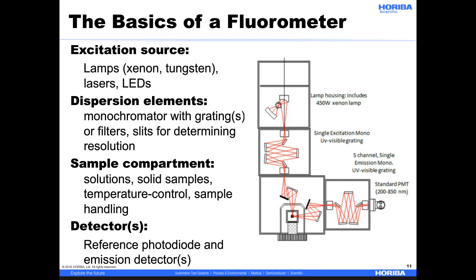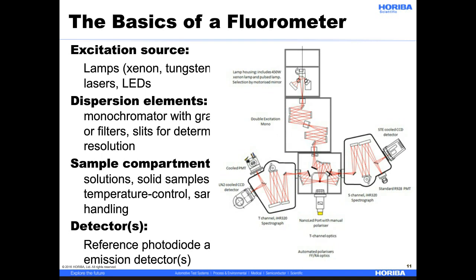After another monochromator to select the emission wavelength, we have an emission detector that measures the fluorescence intensity emitted. Standard detectors are typically in the UV-visible range, but extended and near-IR detectors are also used. Fluorometers typically use photomultiplier tubes, but some use CCDs and array detectors. A basic fluorometer can be varied with many different illumination and detection options, depending on the application.